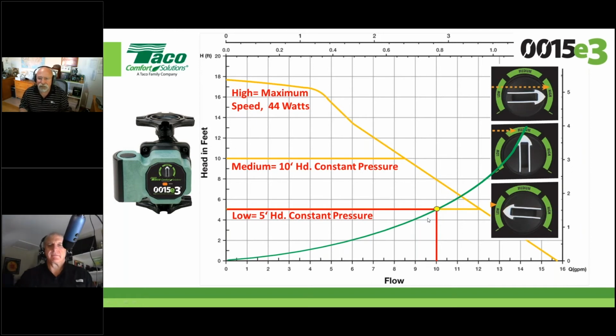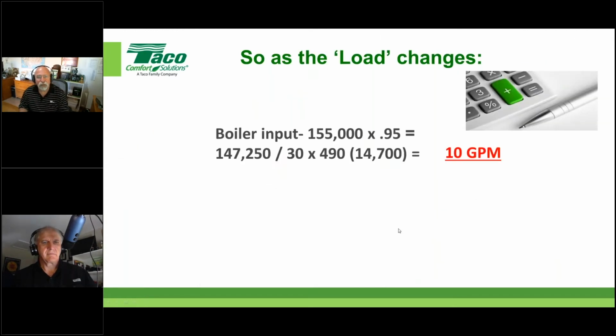So again, just understand in this case, I would take a 0015 E3 and put it at 5 foot of head constant pressure. It'll run just fine. Don't expect it to move up and down because it won't, but it'll operate similarly to what that 0018 will. So anyway, just remember this, that we're shooting for this when we do a fixed speed circulator like we're talking about.